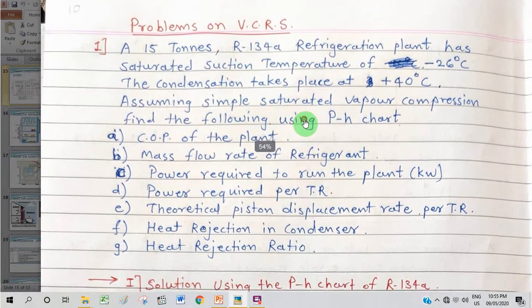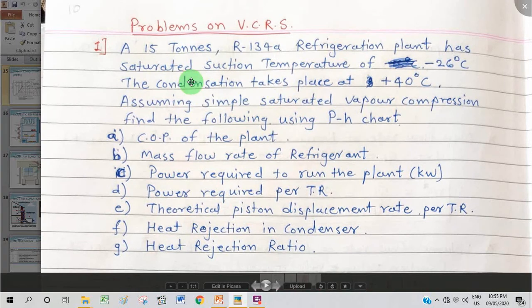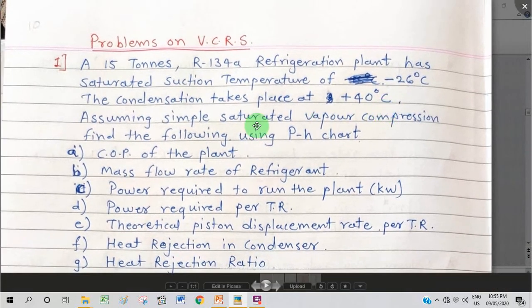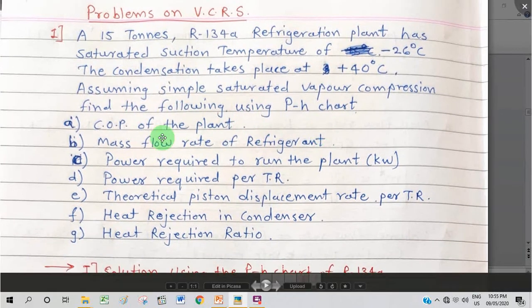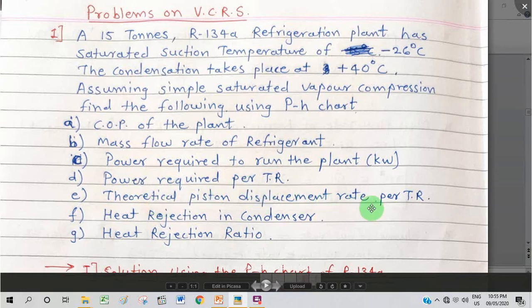You can read the problem statement on screen: a 15-ton R134a refrigerant plant has a saturated suction temperature of minus 26 degrees Celsius; condensation takes place at plus 40 degrees Celsius. Assuming simple saturated vapor compression, find using the PH chart: COP of the plant, mass flow rate of refrigerant, power required to run the plant in kilowatts, power required per TR, theoretical piston displacement rate per TR, heat rejection in the condenser, and the heat rejection ratio.